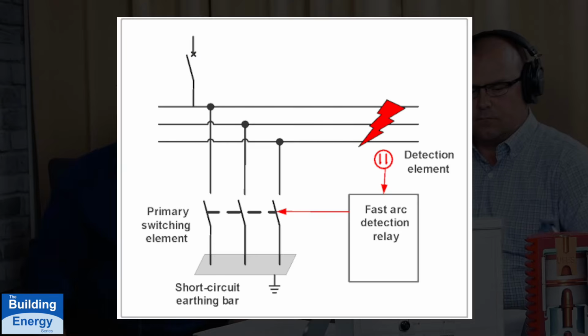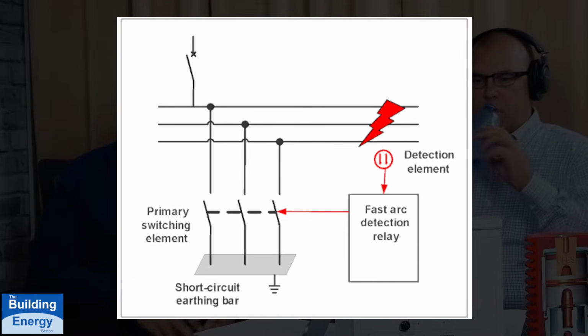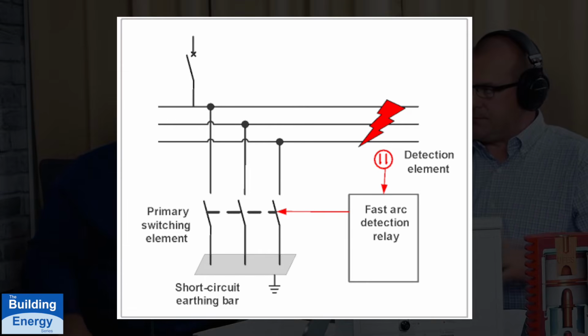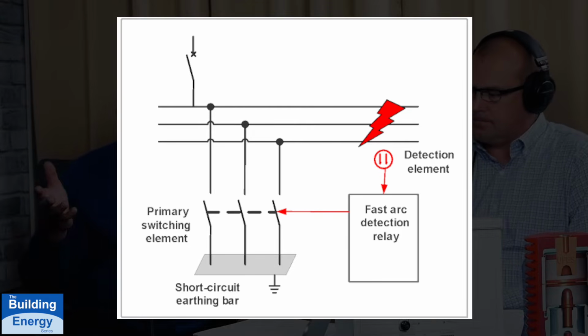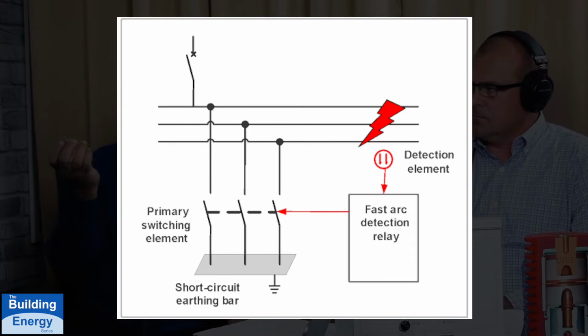The other technology that we have at ABB is called the ultra fast earthing switch, and I would say it's a very innovative technology. When you're undergoing an arc event, it will basically direct the arc current to ground and collapse the arc voltage. What would normally take an upstream breaker, if you don't have any arc flash protection relays, up to 200, 300 milliseconds to clear, could be less than 100 milliseconds if you have arc flash protection relays.